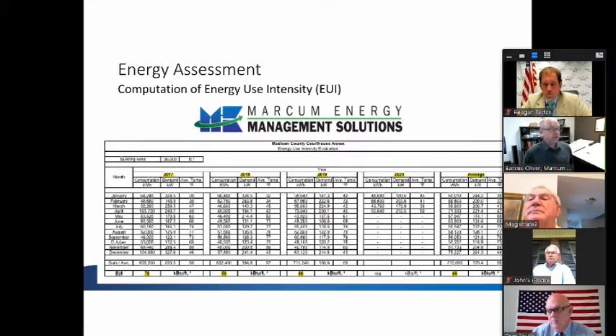Our other company, Marcum Energy Management Solutions, studied your utility bills. And basically, I want you to take two things away from this. For the last 3 years, the building has scored an EUI, or that's your energy use intensity, of 78 in 2017, 59 in 2018, 66 in 2019, for an average of the last 3 years of 66 kBtu a square foot. That kBtu per square foot is an EUI. It is a unit that engineers assign to a building to assess how efficient the building is. Just like we say miles per gallon for our automobiles, engineers say, what is the EUI for the building? What this tells me, I'm going to get to a summary page and we'll discuss what this means. But basically, we're benchmarking how the building has been doing on efficiency.